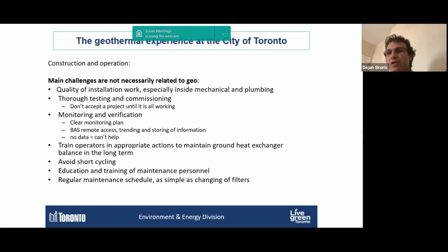A clear monitoring plan is essential, and again that's not directly related to geo. Simple things like BAS access, remote access, and having the BAS trend and store information matter a lot. So if you have to do troubleshooting, you're actually able to figure out what happened. If there's no data, we can't help, or it's very tough to help. You have to go and do forensic analysis, which takes time and cost, while the building is probably lacking heat or not being cooled properly.